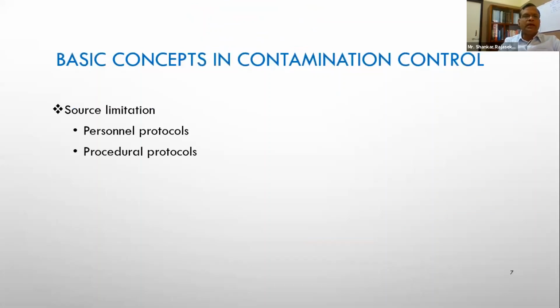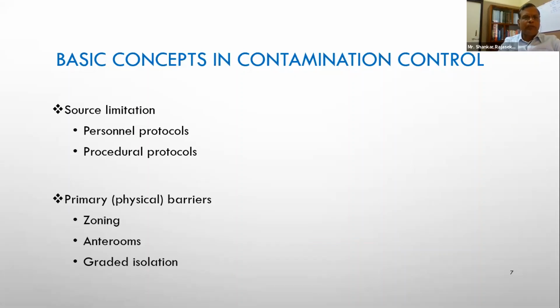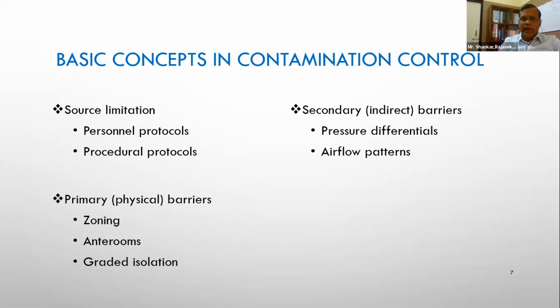So what are the basic concepts? Of course, we need to limit the source, personnel protocols and procedural protocols like zoning and other kinds of applications. We talk about physical barriers, primary barriers which are physical. We talk about anterooms and graded isolation. We have the secondary barriers, which is going to be very important especially for the ultrafine particles and the very small bacteria and viruses, by maintaining pressure differentials. Because even a closed room, a room with a closed door, will have gaps and crevices through which the contaminants or the infectious agents can leak inside.